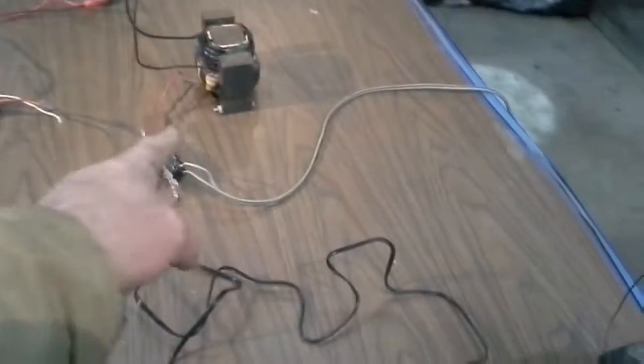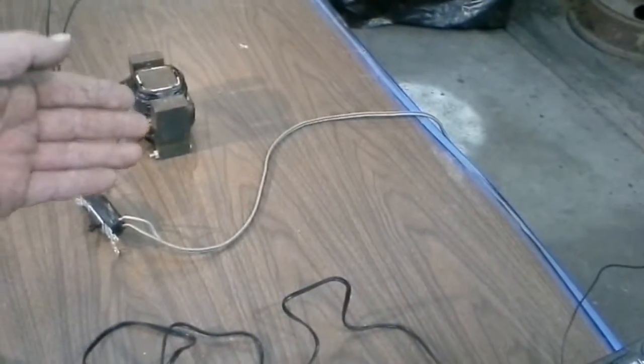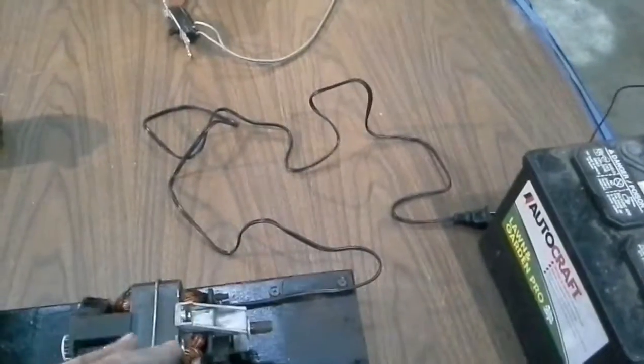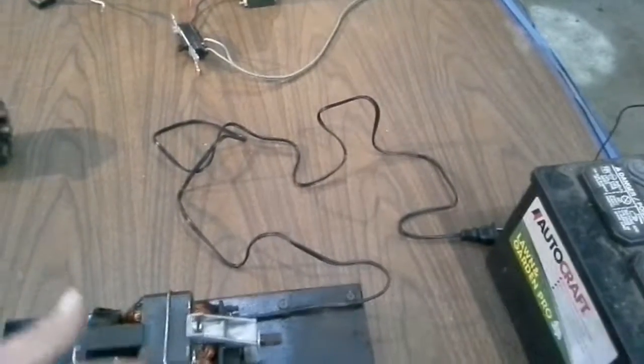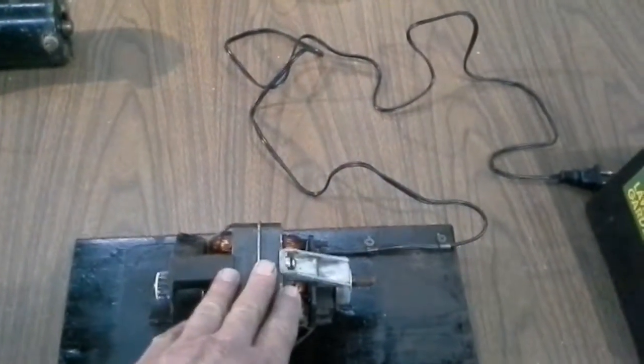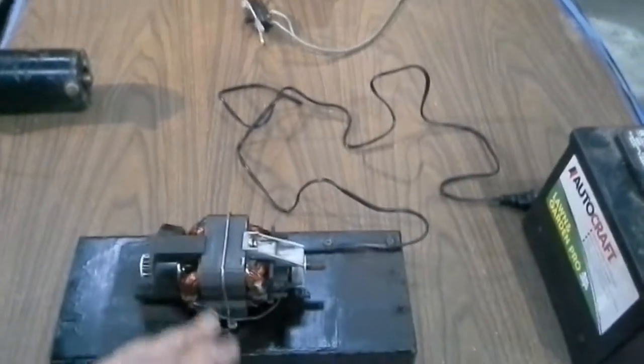At home or wherever, anytime you run a motor off a lower voltage than it's intended for, you can get heat and damage the motor. When you run them on low voltage, they don't have the torque or power. You can stop them easier or quicker than when they're run on the correct voltage, AC or DC either one.